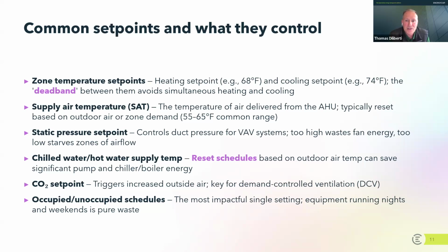The dead band is the range of temperatures between heating and cooling when the building is not actively heating or actively cooling. So it's a range of temperature, in this case between 68 and 74, where again, the building is not actively heating or cooling. So it's dead to the systems. The systems will still be ventilating and they'll be introducing air in order to keep the occupants comfortable.